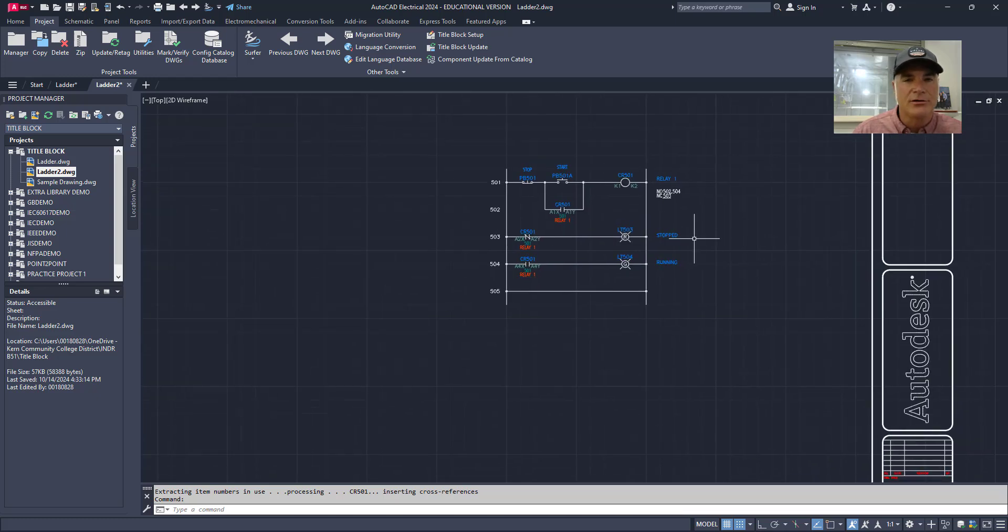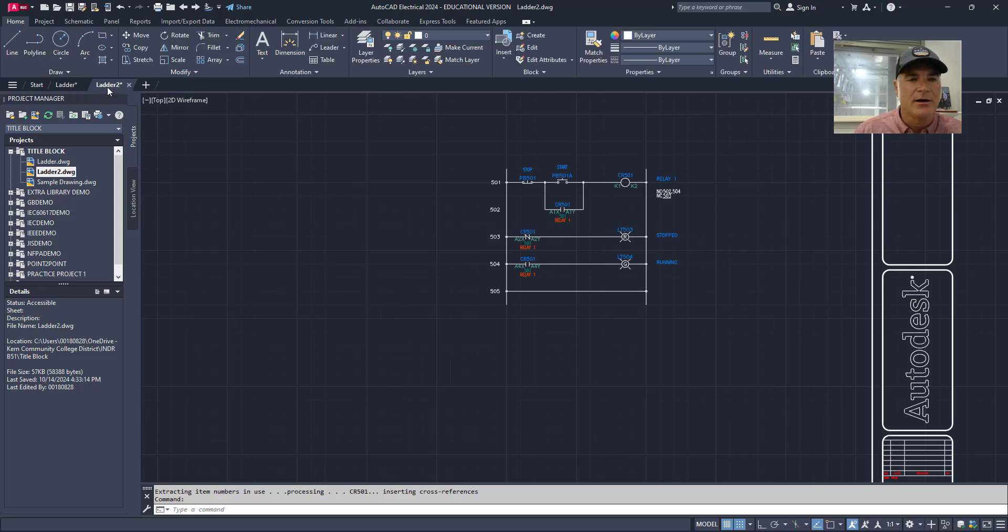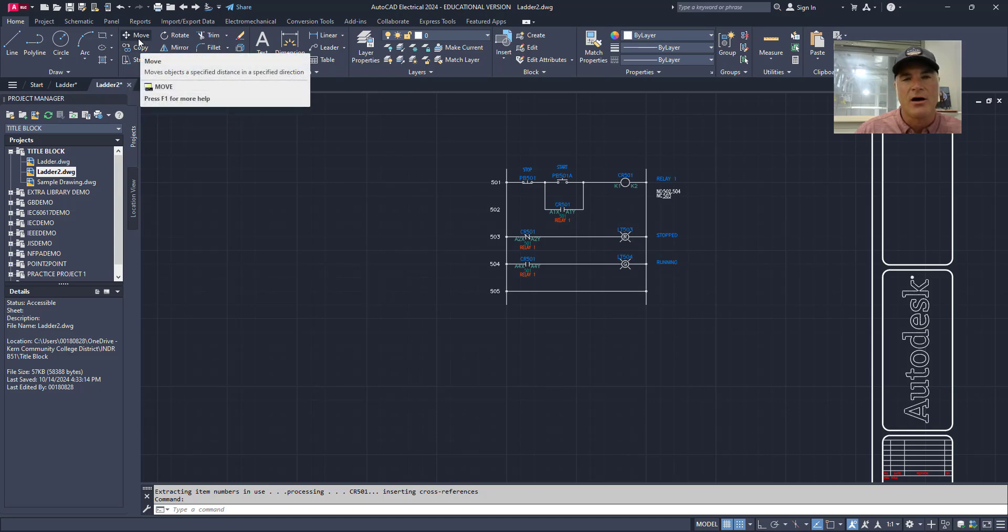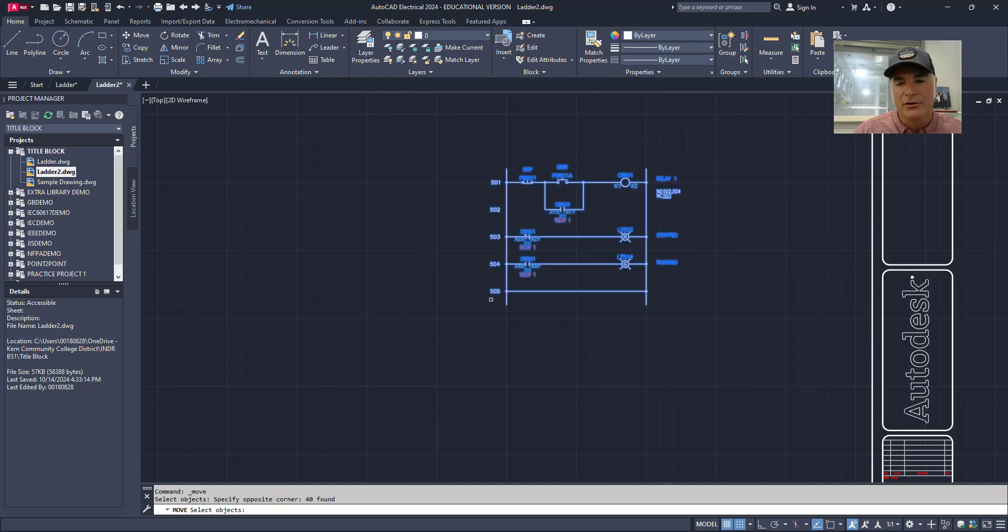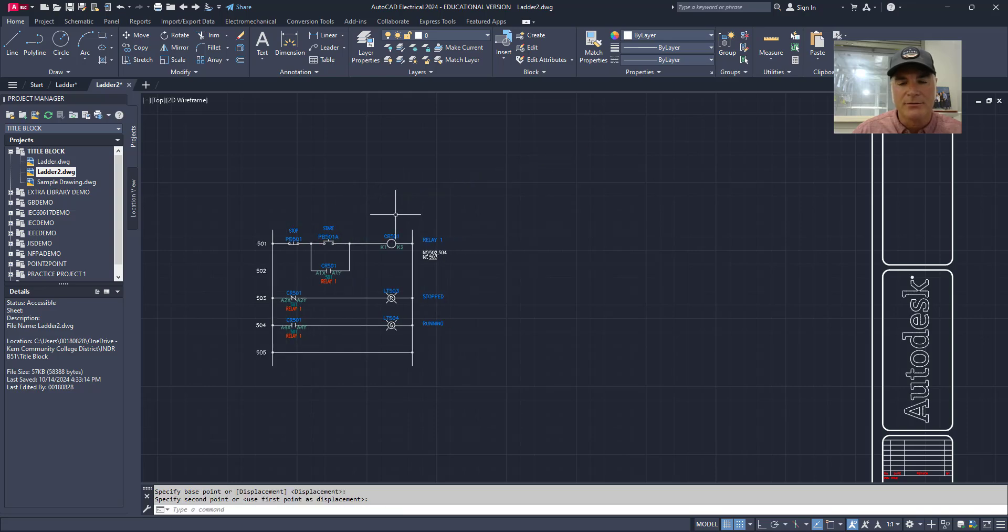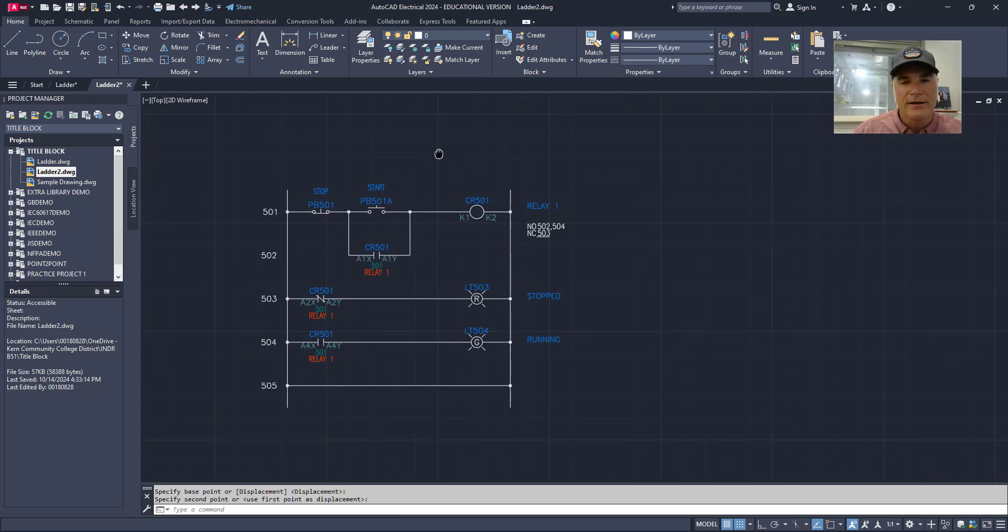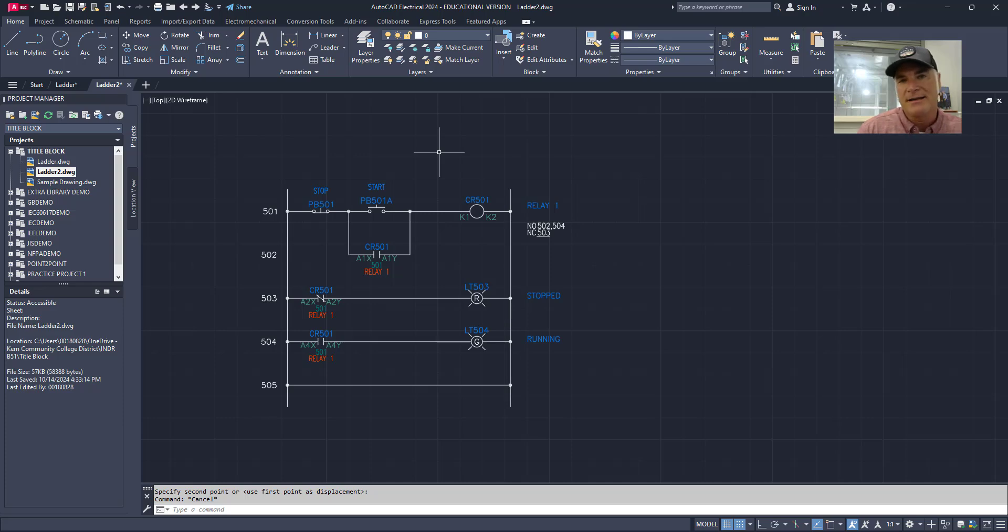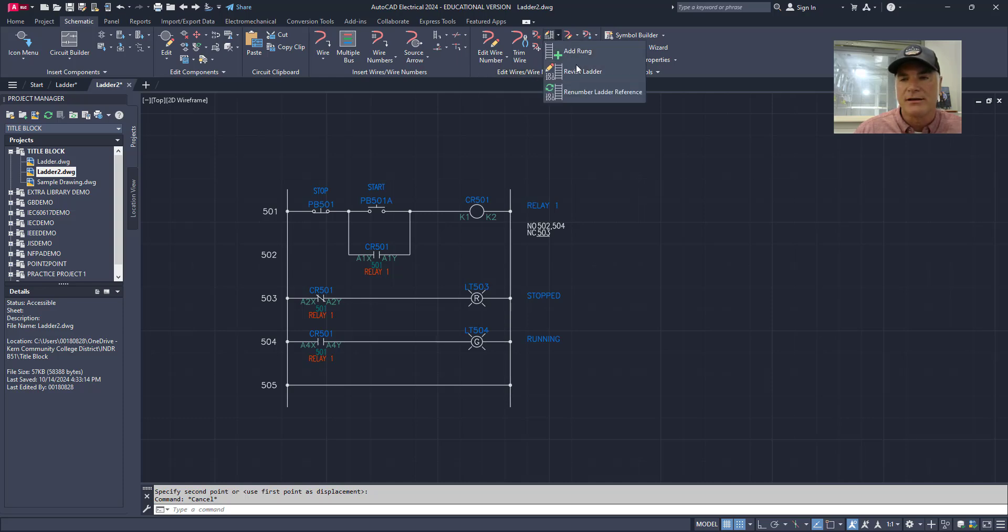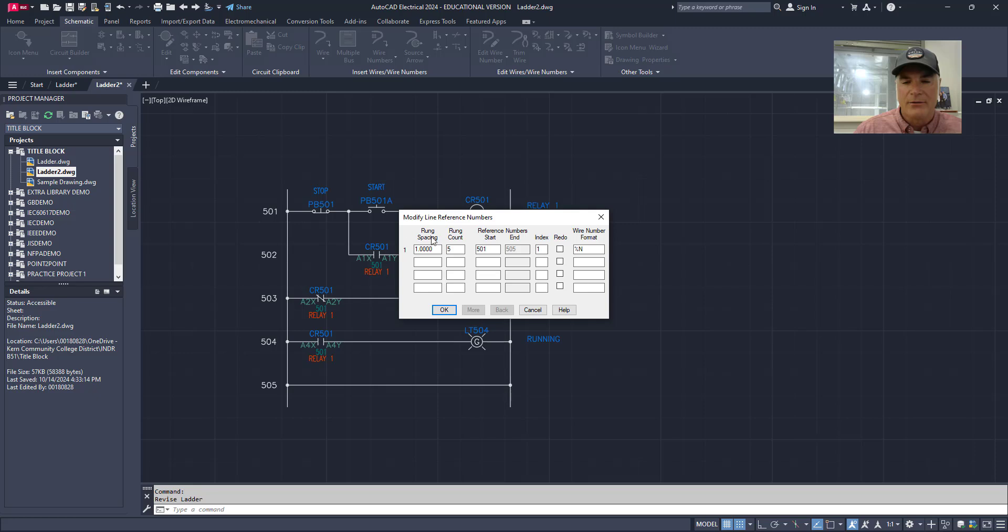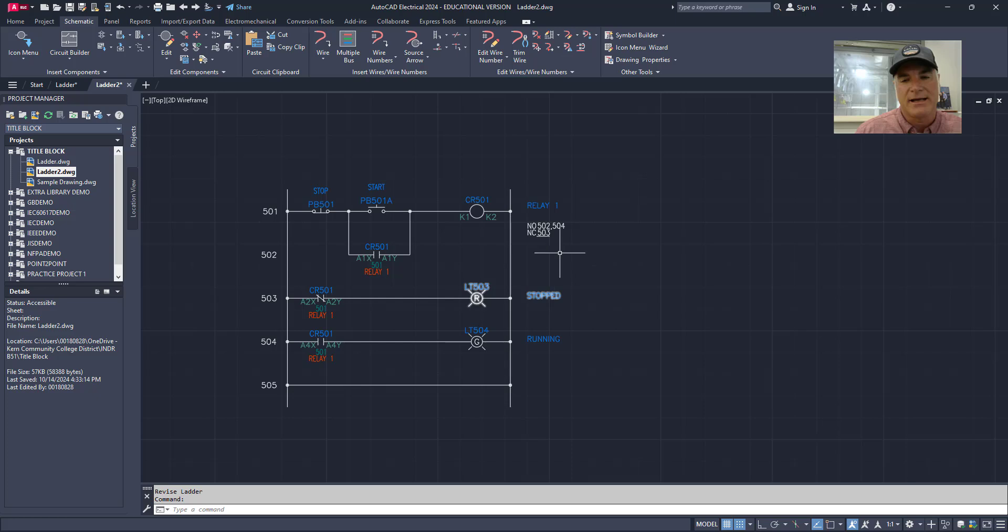Now the last thing that you might need to do is you might need to move a ladder from one place to another. To do so you can use the regular move command inside of AutoCAD. And you'll just simply make sure that you capture everything in your ladder including all of the numbers, all of the components, all of the text over here on the side. And you can move it wherever you need to move it to. But when you move it, AutoCAD loses place. It doesn't know where that is. So in order to finish out the process and let AutoCAD update the database behind the screen that you can't see, you'll go back to the schematic tab, choose the edit wires and wire numbers tool, and choose the revise ladder tool. And once you do that, just bringing this dialog box up refreshes the database and makes AutoCAD verify where this is in space. So at this point you can choose cancel.